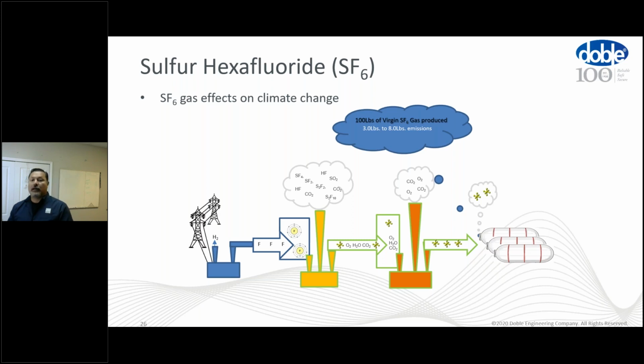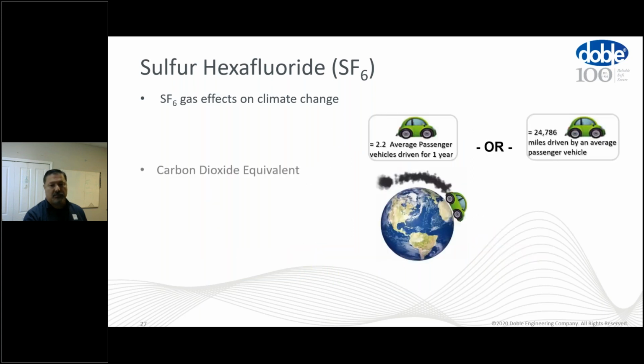SF6 produced can create between 3 to 8 pounds of emissions. So think about that, 3 times 22,800 or 8 times 22,800 of emissions. So quite a bit of an impact on climate change when virgin SF6 gas is produced. That equivalent 1 pound of SF6 is equal to 10.3 tons of CO2. So in other words, if we drove 2.2 cars, an average size vehicle, for a year, we would create that much emission. Or driving, again, an average size vehicle, 24,786 miles, we would create that much of an emission. So keep that in mind. That's the equivalent of that 1 pound of loss of SF6.